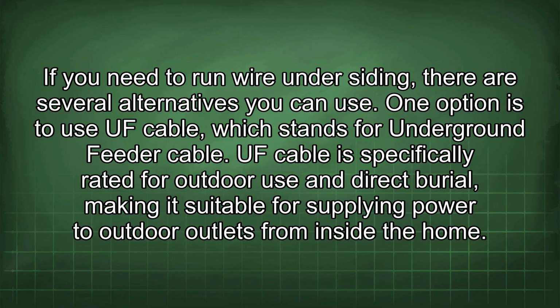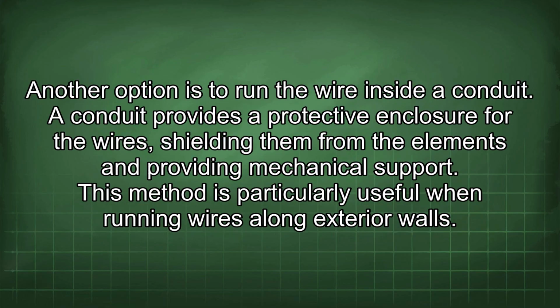One option is to use UF cable, which stands for underground feeder cable. UF cable is specifically rated for outdoor use and direct burial, making it suitable for supplying power to outdoor outlets from inside the home. Another option is to run the wire inside a conduit. A conduit provides a protective enclosure for the wires, shielding them from the elements and providing mechanical support. This method is particularly useful when running wires along exterior walls.